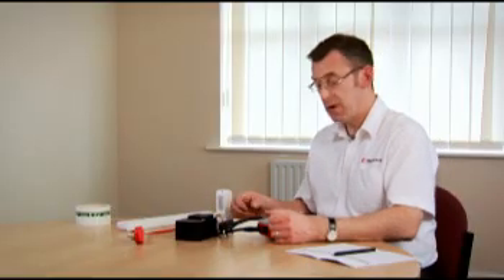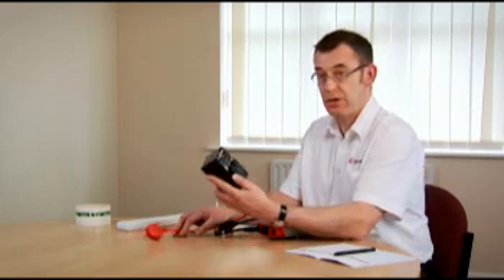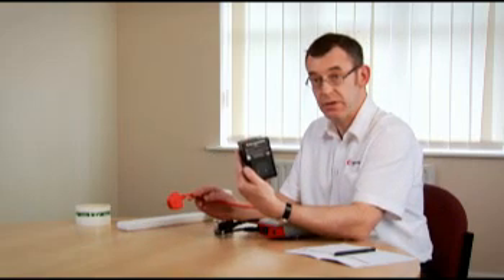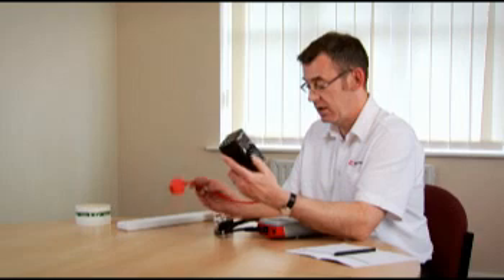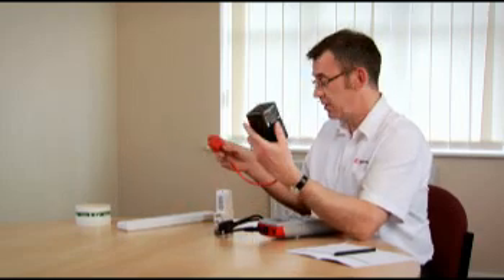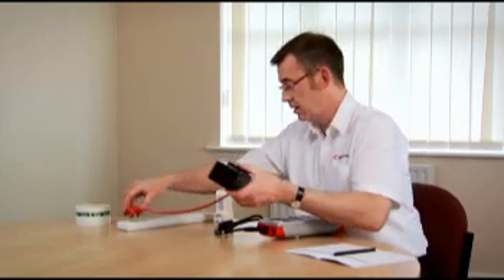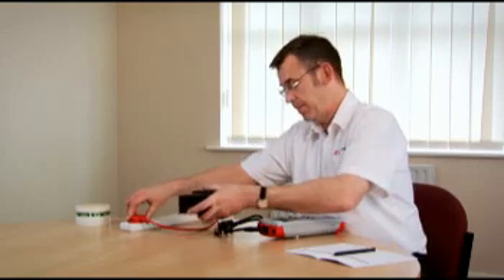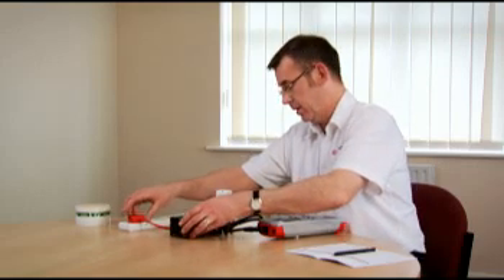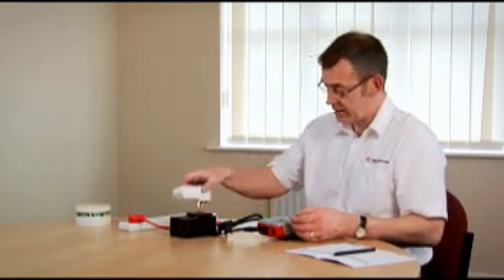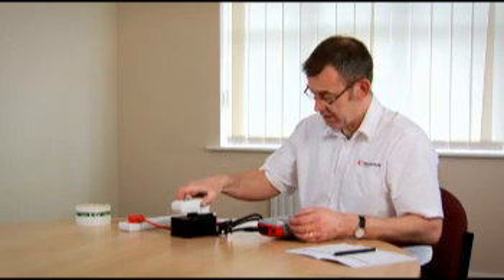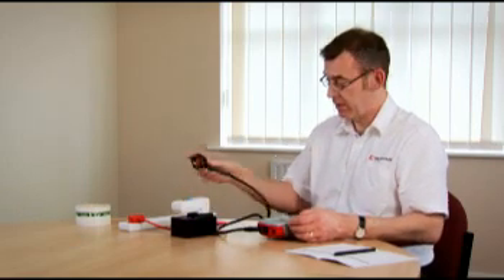That problem can be overcome by using this Seaward non-trip adapter or non-trip box to give us an isolated supply. So the non-trip adapter is plugged into the main supply. The portable RCD is then connected into this test supply and the test instrument plugged into the RCD.